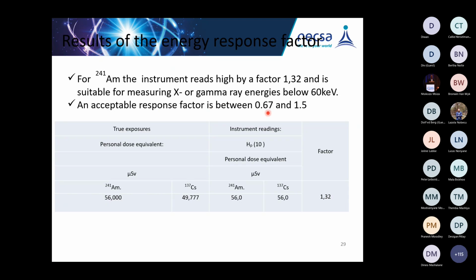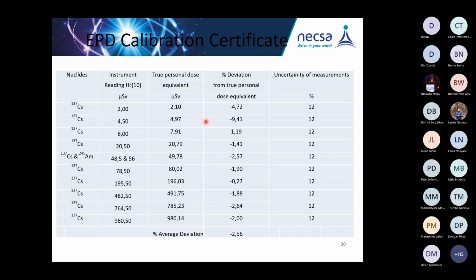And then with the cesium and the americium, we're determining the energy response factor. A good energy response factor varies from 0.67 to 1.5. So if you look at 1.32 for this specific instrument, it shows that the instrument is still in good condition. These are the readings that you will see. This is your instrument response, and this is the true dose. The instrument was given this dose over a time, and then the instrument produced that. And this is the percentage deviation, and that is the uncertainty, plus or minus 12, with which you can determine your upper and lower limit when you apply the uncertainties. These are actually the results, and this is the overall result of the percentage deviation.